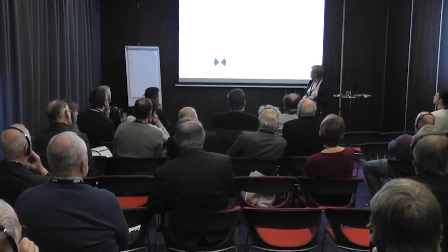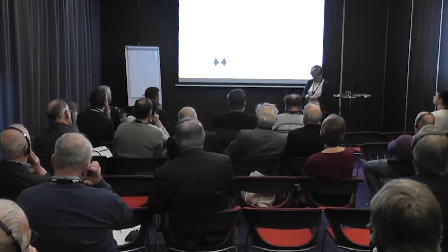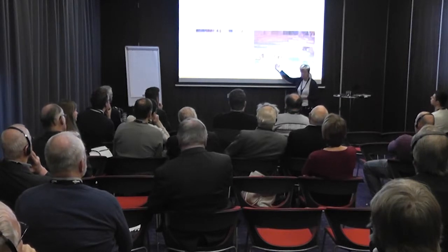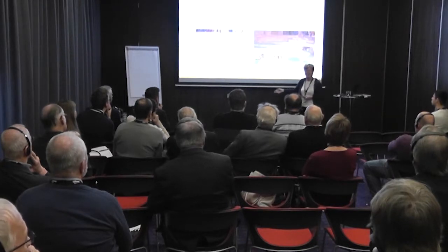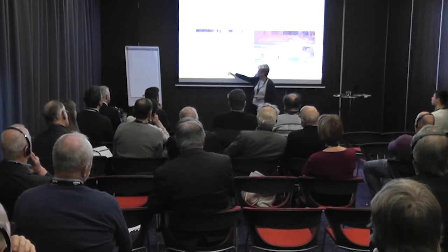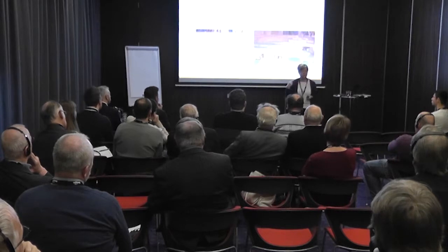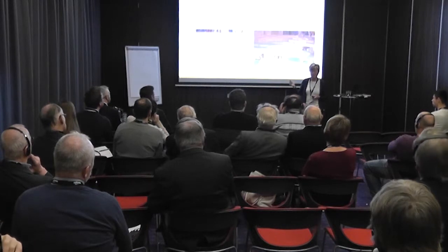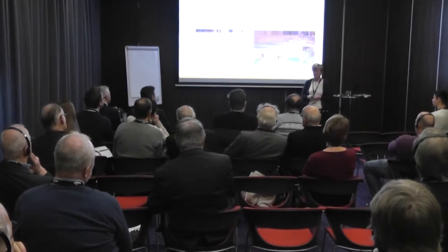What was not that normal is that when this was built, it was not built as it was drawn. So we ended up with a lot of woodwork that was used that we did not expect and that we did not see on the drawings. Maybe this would have been better today with a BIM, maybe it would have been more correct. So we ended up with these openings. They were 2 or 3 centimeters lower than in the design. So in this area where sound and climate had the main focus, it was a terrible situation.